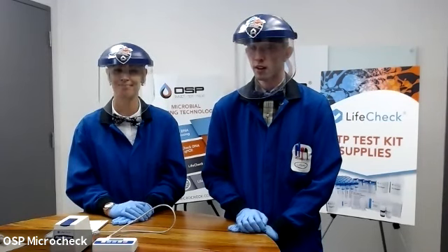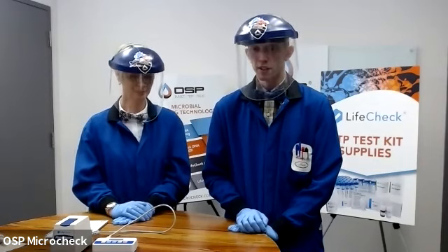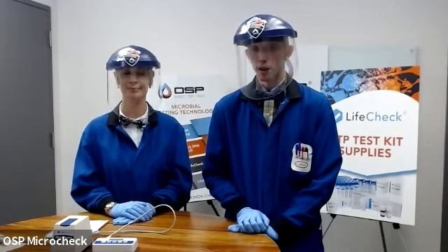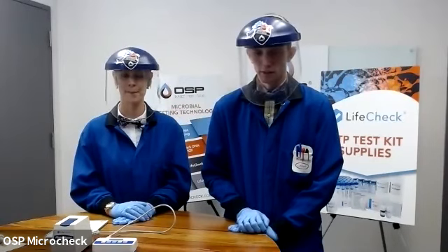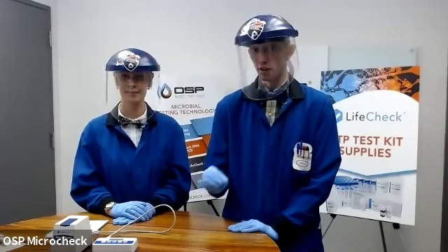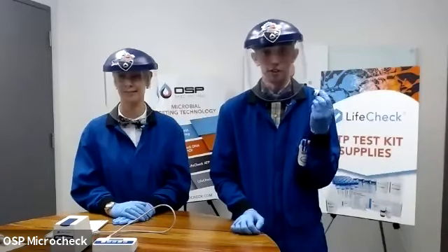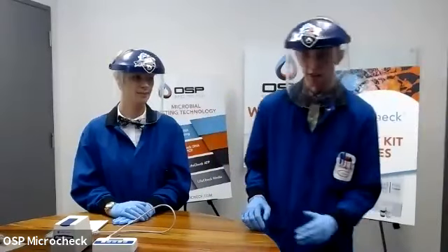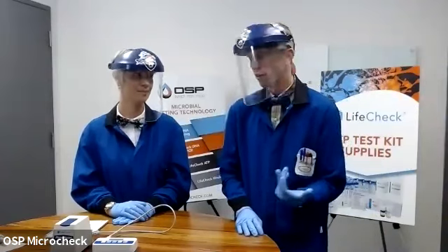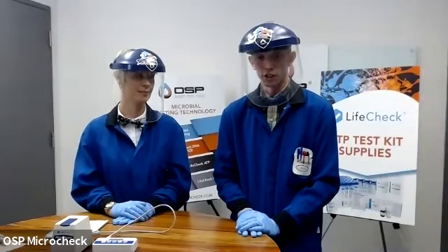So the big one that I have seen out there is with oxidizing biocides, things like chlorine dioxide and bleach. If you attempt to treat a water with your oxidizer and immediately test it, and I mean immediately, as in within minutes afterwards, the presence of that oxidizer within that water will disrupt the activity of the enzyme, because that enzyme or protein is a living thing of sorts, and it will denature from the addition of that type of biocide. If you can wait a couple hours, even 30 minutes starts to show some reduction in that.